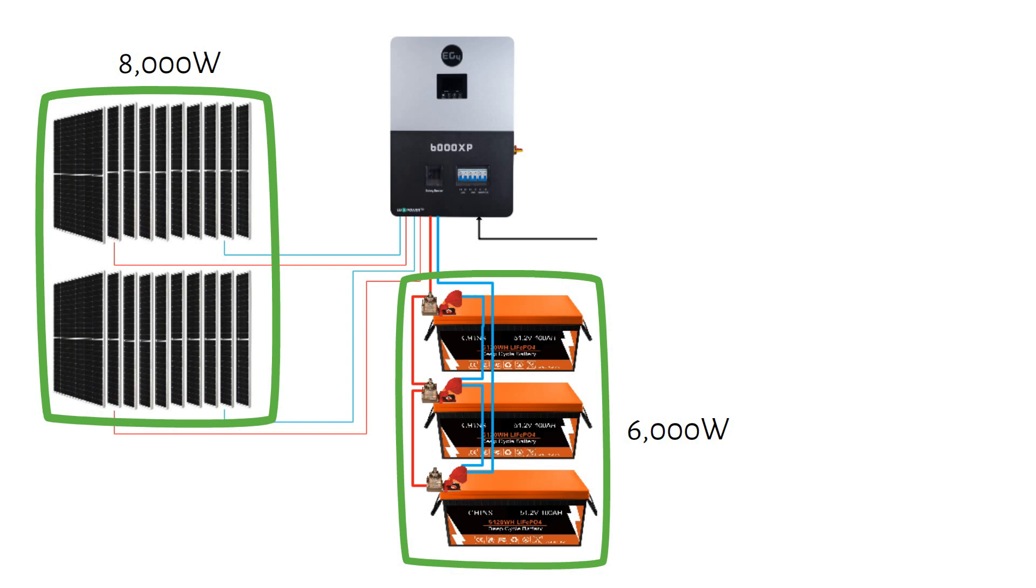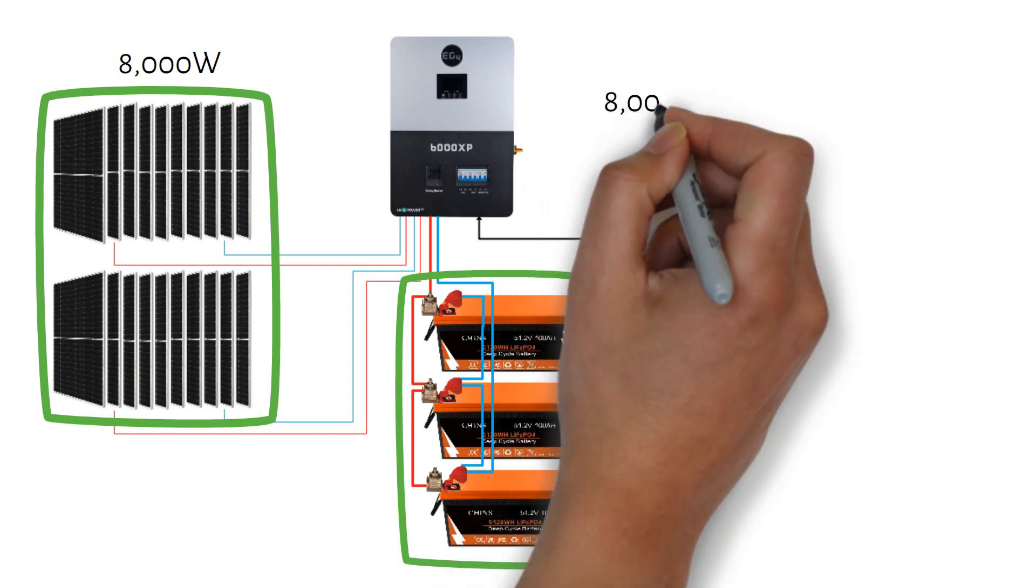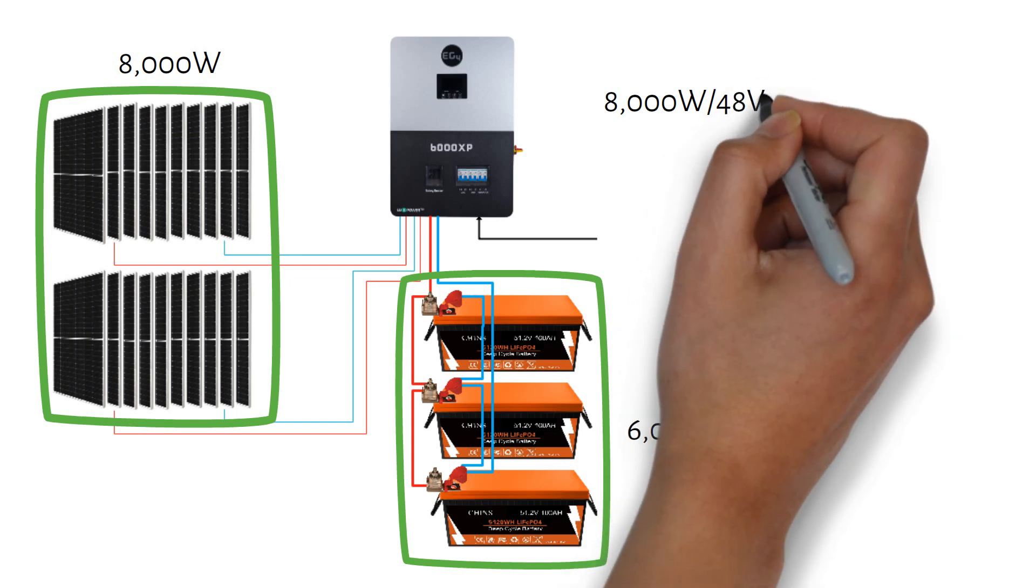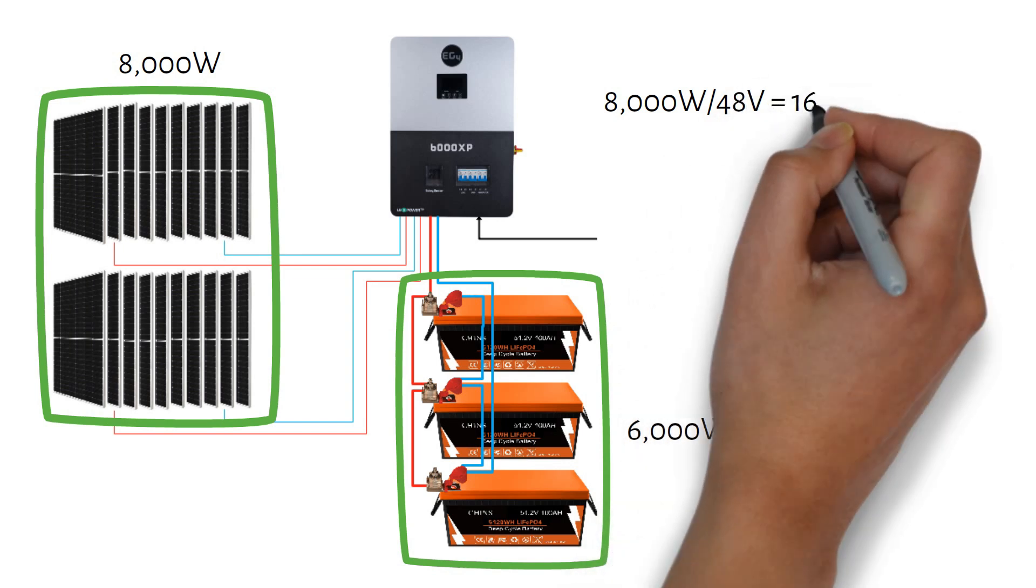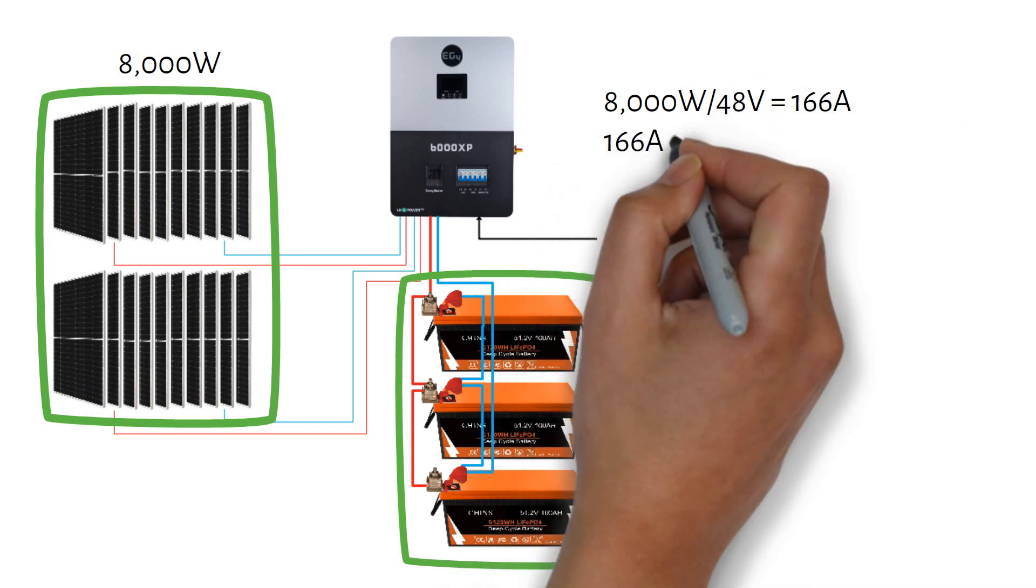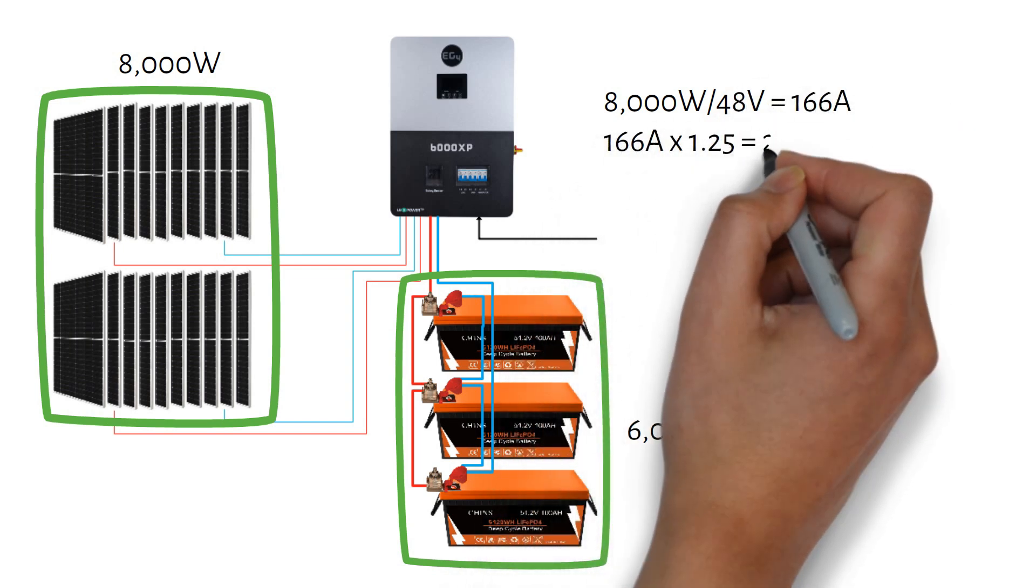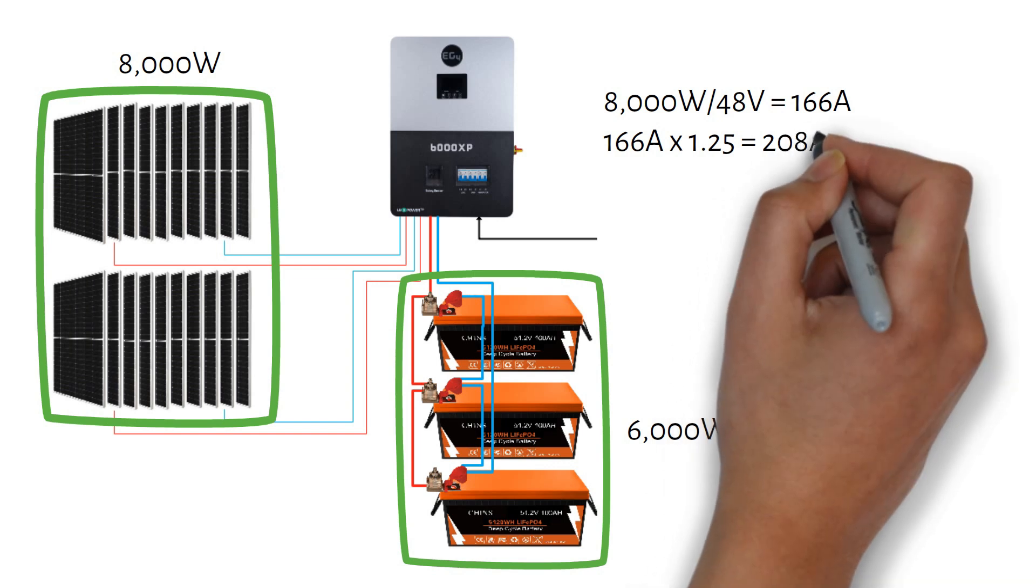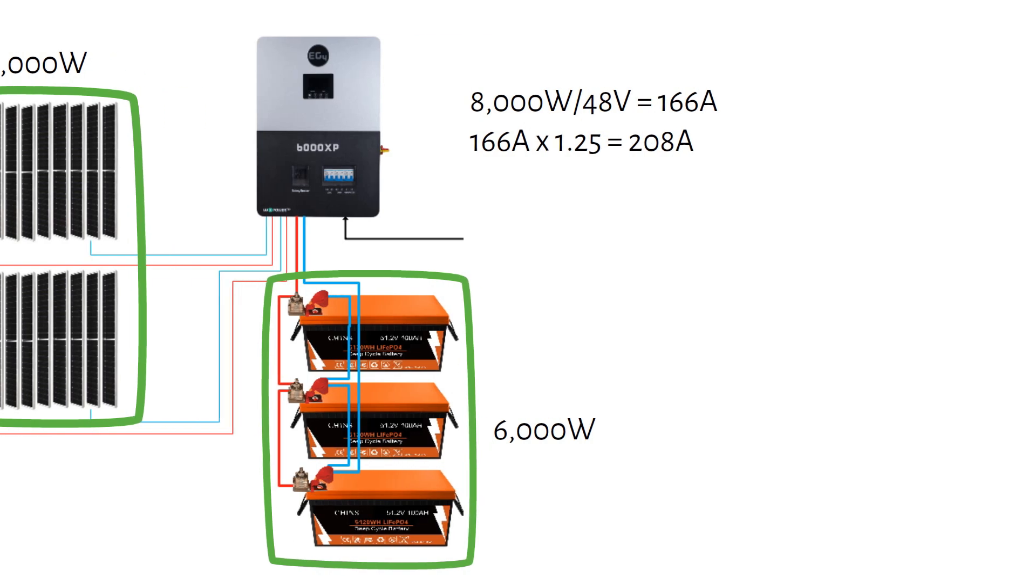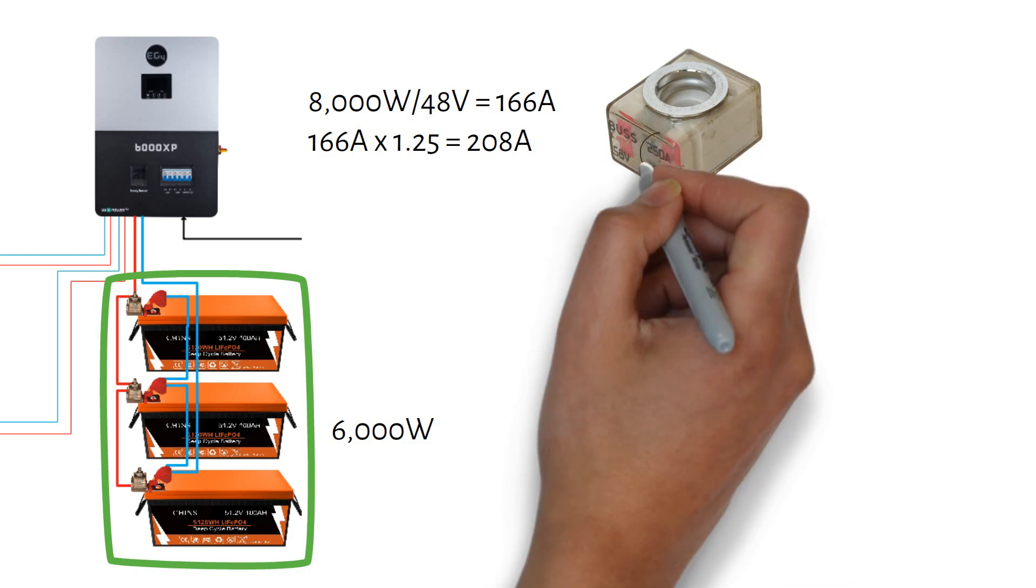If we divide 8,000W by 48V, we get 166A. Then, we will apply a safety factor of 1.25 and we get 208A. We will use a marine rated battery fuse. A fuse rating higher than 208A is 250A.